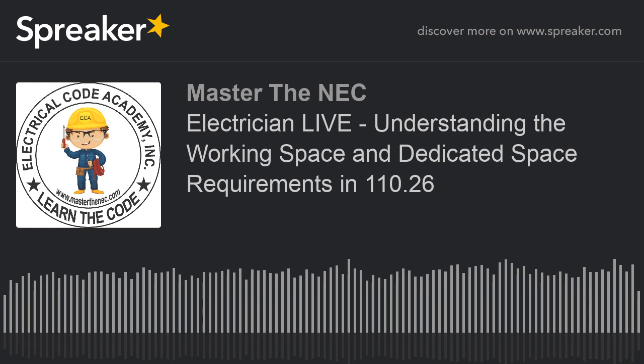So what we're talking about is applications that might be in crawl spaces, low basements that wouldn't qualify as a basement, but it's kind of like a basement with a limited height access, or again, above a suspended or dropped ceiling application. So it says, limited access, A4. It says where equipment operating at 1,000 volts nominal or less to ground, common theme here, and likely to require examination, adjustment, servicing, or maintenance while energized is required by installation instructions or function to be located in a space with limited access, all of the following shall apply.